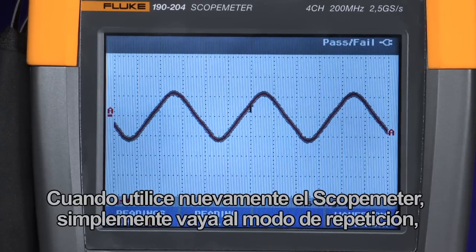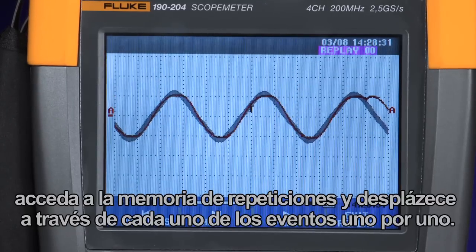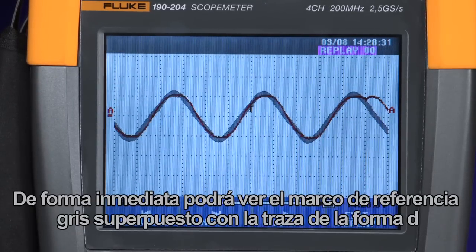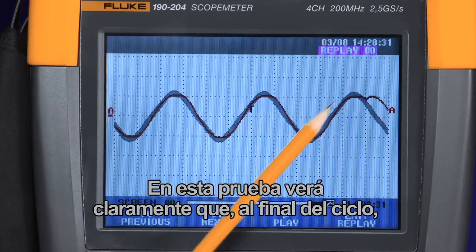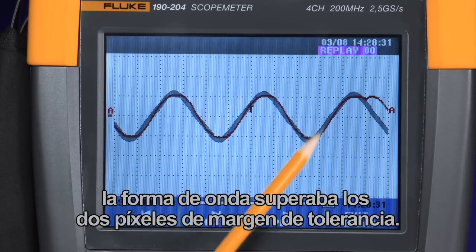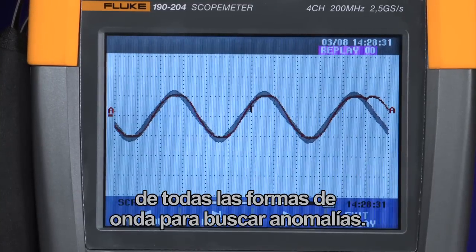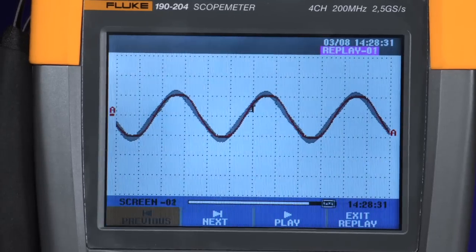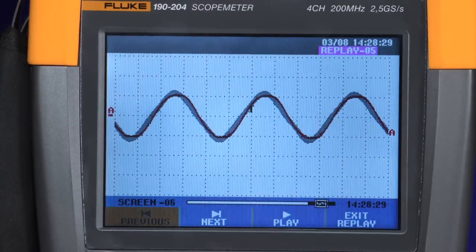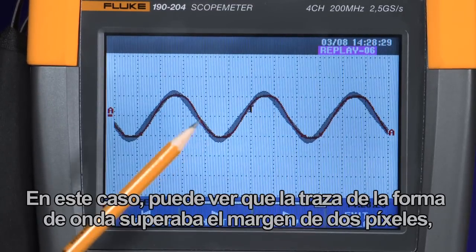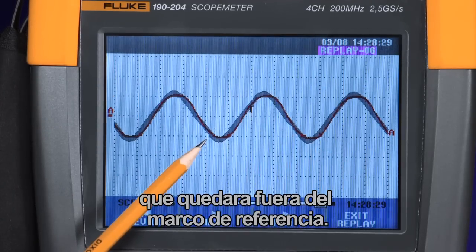When you return to the scope meter, simply go to the replay mode, access the replay memory, and you can scroll through each of the events one by one. Immediately you can see the gray envelope overlaid with the waveform trace the scope has captured. In this test, you can see clearly that at the end of the cycle, the waveform exceeded the two pixel tolerance window. You can also go through each of the memories and inspect every waveform looking for such anomalies. You can see that the waveform trace exceeded that plus two pixel window, making it sensitive enough to capture just about any anomaly that falls outside that envelope.